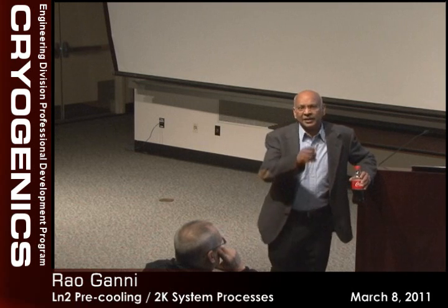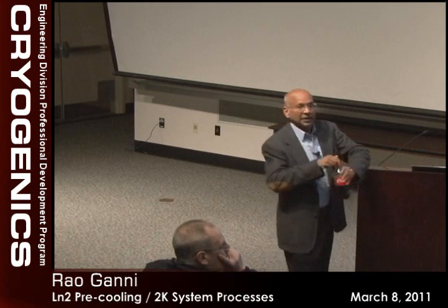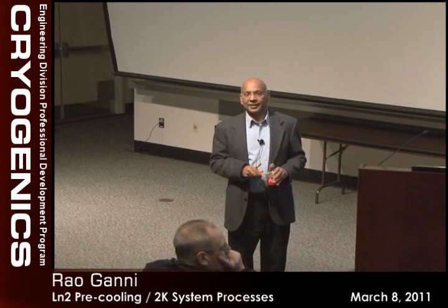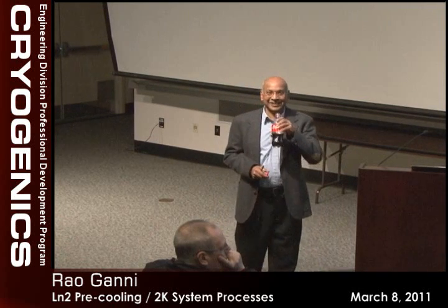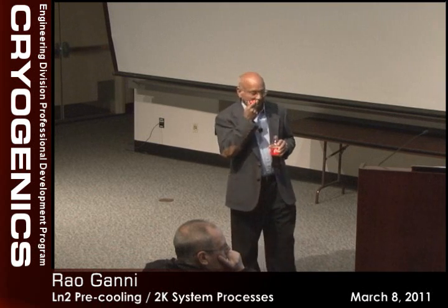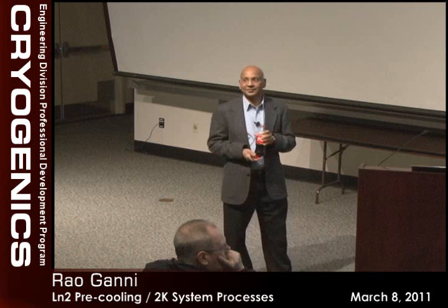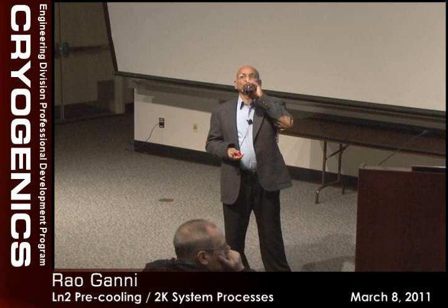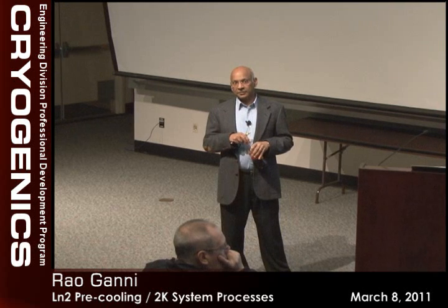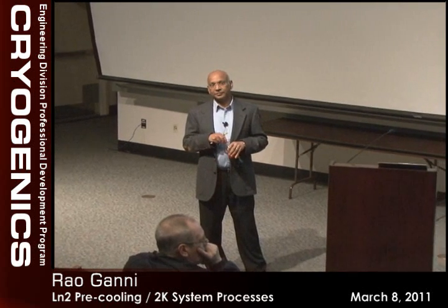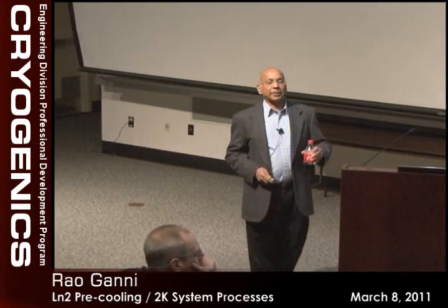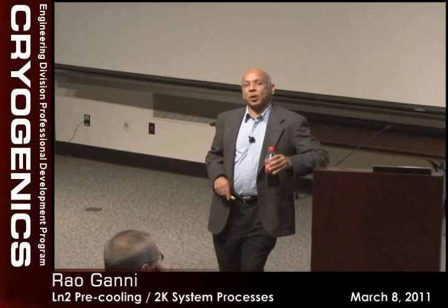Anyhow, the biggest difference between SNS and ours is the high frequency. The motors of both projects are the same. What that meant is that the motors for SNS, for the same stages, were oversized for the application. The SNS flow rate is half ours. So we're talking about effects of power factors on motors when the motors are lightly loaded. But that's not where our problem was.